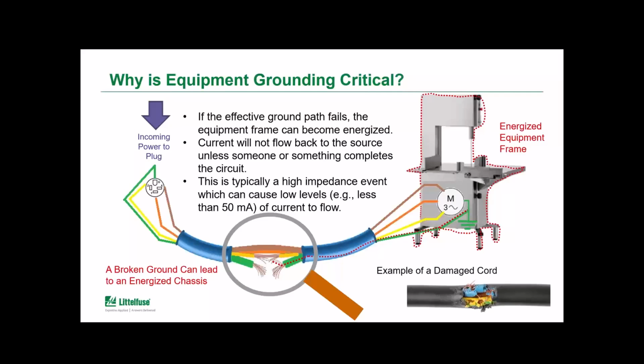Now, in that case, the frame of the equipment can become energized, just waiting for someone to touch it and for their body to perhaps provide that alternative path through their body to another grounded surface or piece of equipment. So when somebody completes that circuit, their body's higher impedance causes much lower levels of fault current than would normally flow if the fault current was going through that effective ground path. That current could be so low through the body that a regular overcurrent device like a fuse or circuit breaker is not able to sense the fault.